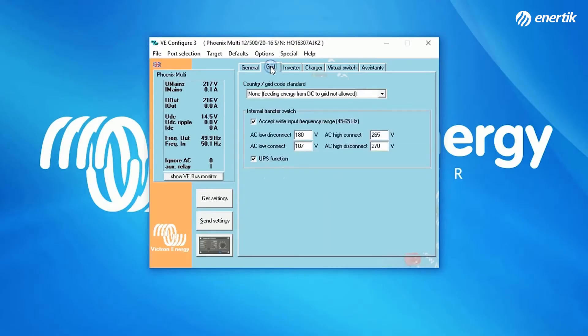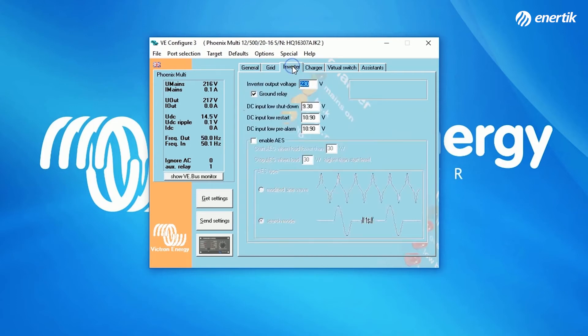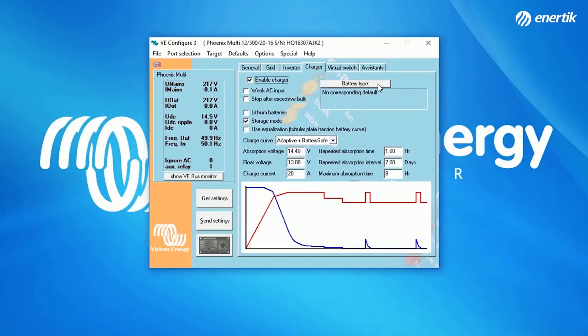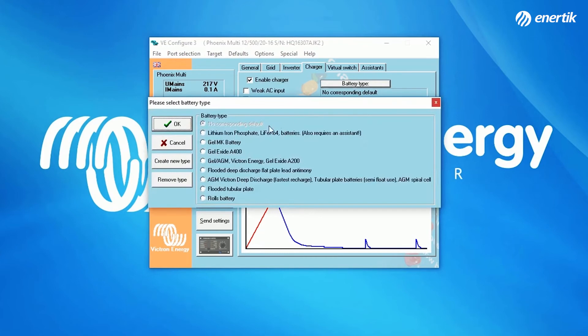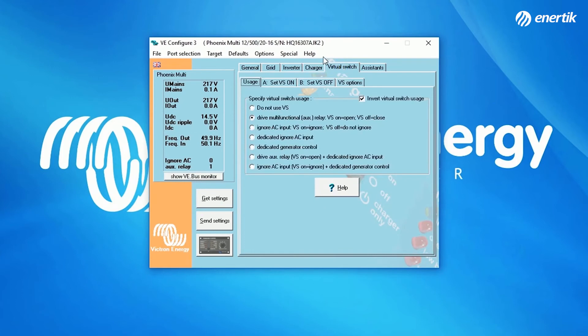The Grid tab enables you to choose your country grid code standard, as the safety protection rules are different for each country. At the Inverter tab, you can make changes related to the inverter — if you don't know what a function means, click on Help, What is this? The Charger tab enables you to make changes related to the charger, such as the battery type, as every type of battery can be charged based on specifications from the battery supplier. At the Virtual Switch tab, you can program alarms, pre-alarms, relays, ignore AC input, and generator start-stop.